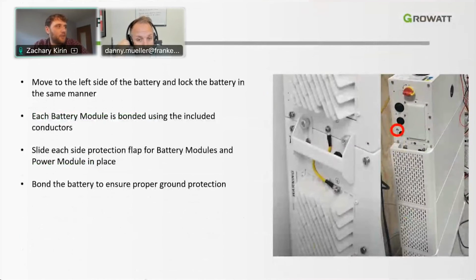So once everything is done on the right-hand side of the unit, we can move to the left-hand side of the battery pack, and we will need to install each of the bonding jumpers between each of the modules, and then install the final trim plates when you're done. The final battery grounding point will be located right here on the left-hand side of the unit. This is the left-hand side. This is not where it is going to the inverter. We'll see a different portion of this in a second.